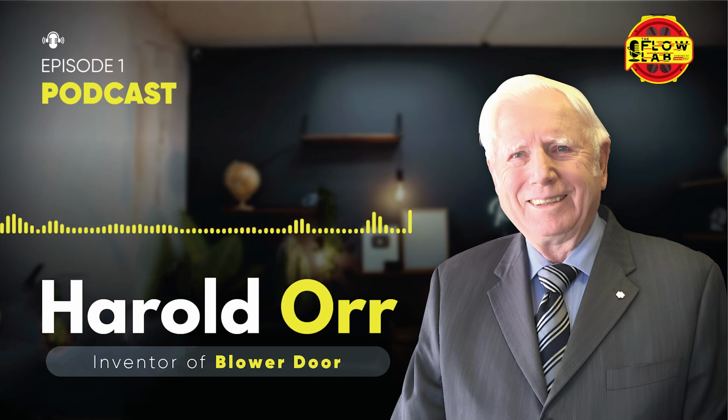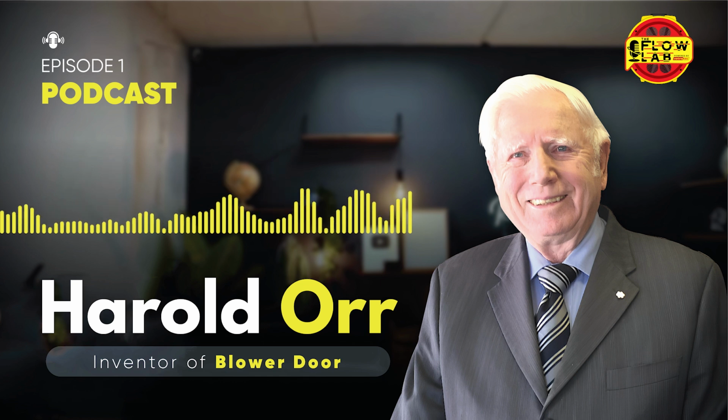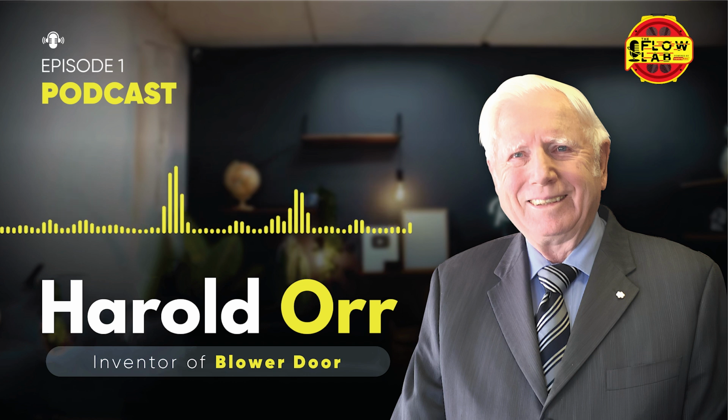And one of the things we did then was to change from using helium as a tracer gas to using sulfur hexafluoride as a tracer gas. Whereas we took 100 cubic feet of helium to do a test on a house, we could do the same test with one teaspoonful of sulfur hexafluoride gas. That's one teaspoonful. And so that made a major difference in terms of cost.